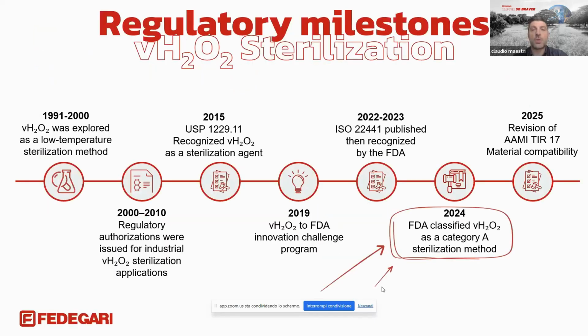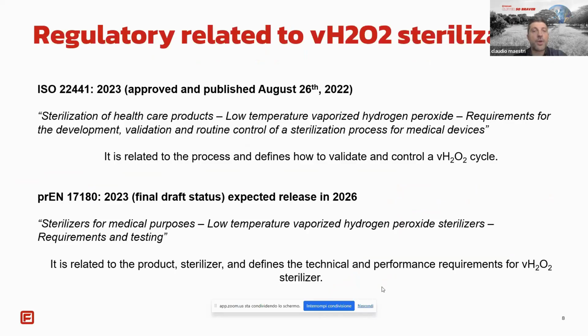FDA announced in January 2024 that it now considers vaporized hydrogen peroxide to be an established method of sterilization for medical devices, recognizing the modality's long history of safety and effectiveness. FDA's recognition of VHP as a Category A sterilization process places H2O2 on par with moist heat, dry heat, ETO, and radiation. In terms of regulation, there is, as we can see here, the ISO 22441, which defines how to validate and control VHP cycles, and, almost close to being released, EN 17180, which defines the technical and performance requirements for VHP sterilizers.